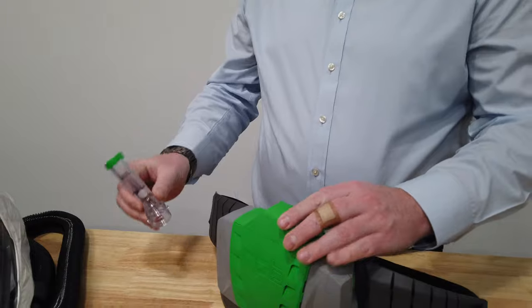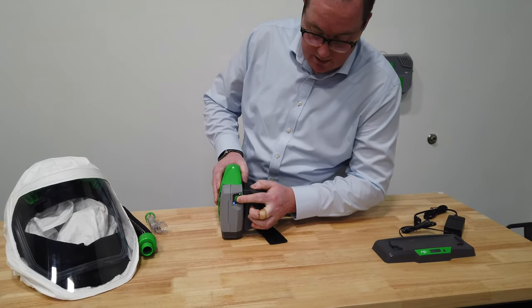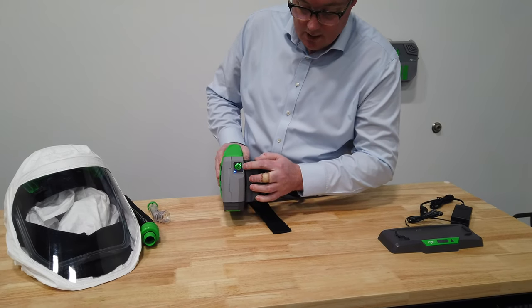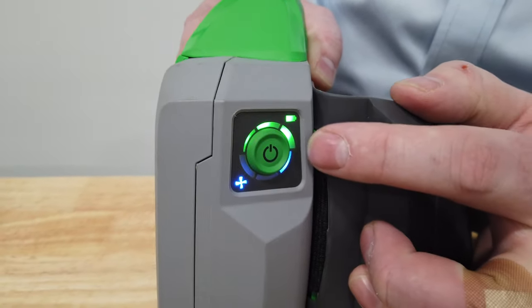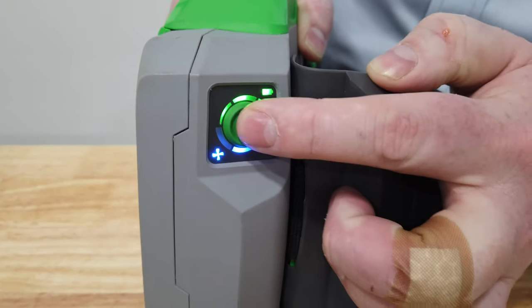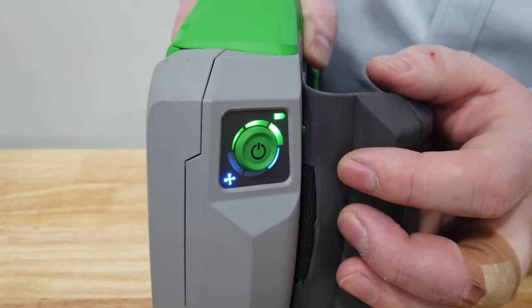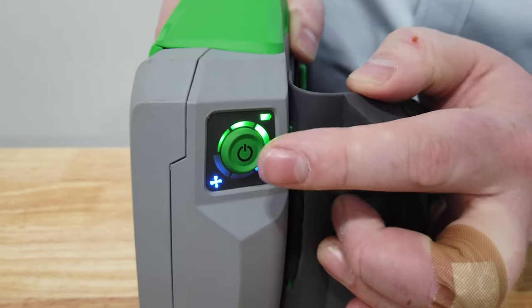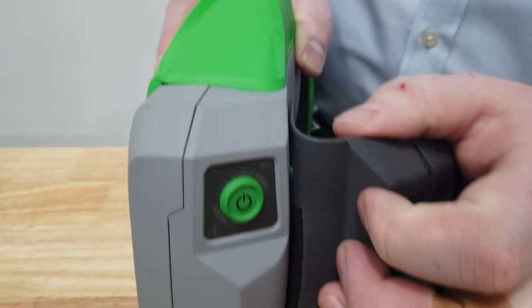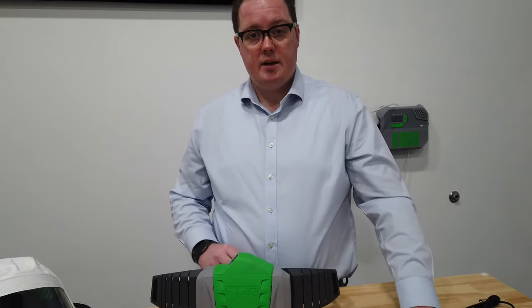Once you've done the test, remove the flow meter from the PX4. On the side of the unit is the on/off button — pressing and holding it turns the unit on. Green lights at the top indicate battery life; blue lights at the bottom indicate fan speed. Pressing the button increases fan speed. Using fan speed one will maximize battery life, giving you around six to eight hours. To turn off, press and hold. The unit will also alarm and vibrate when the battery needs charging.